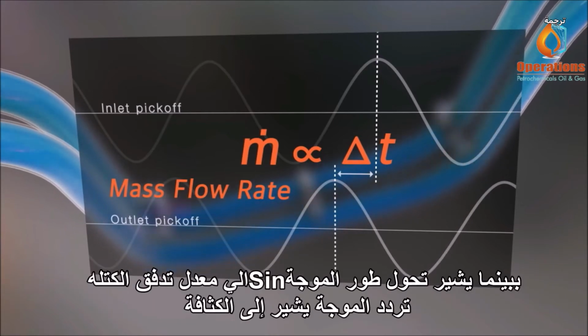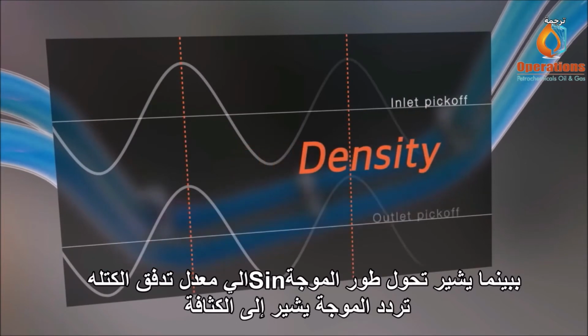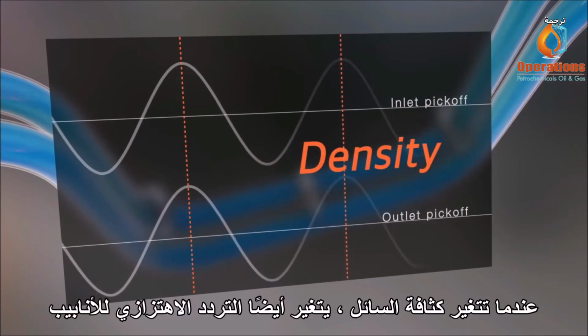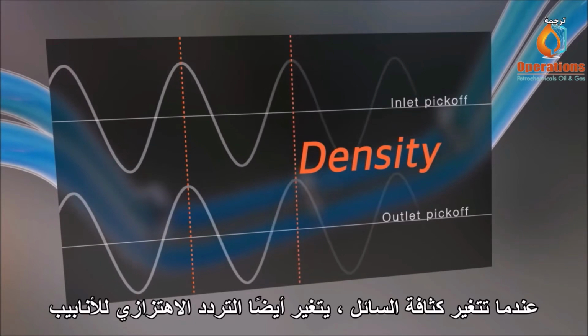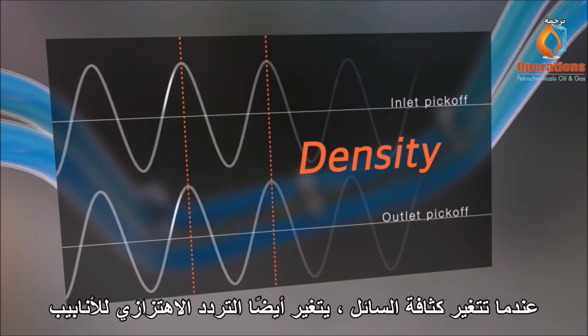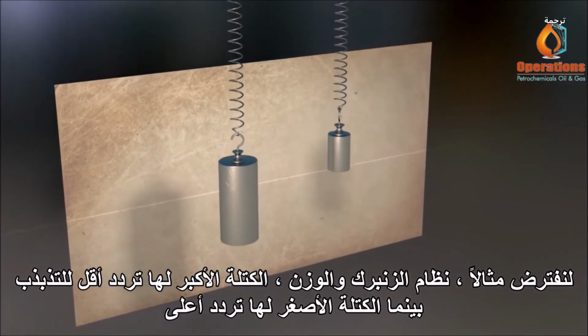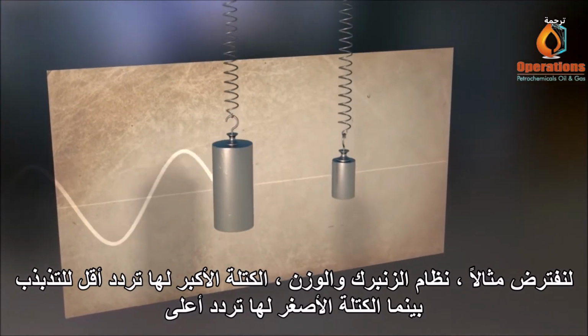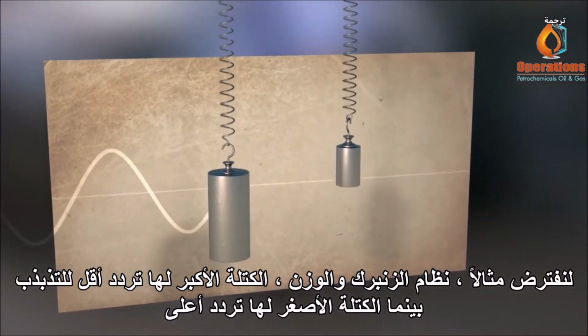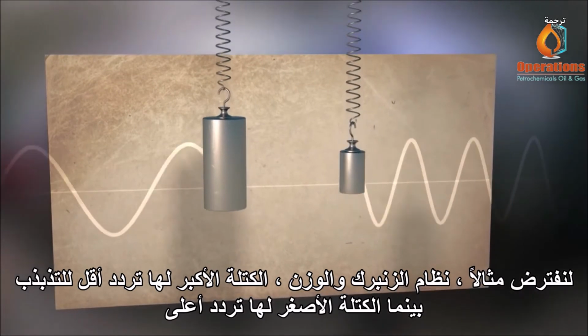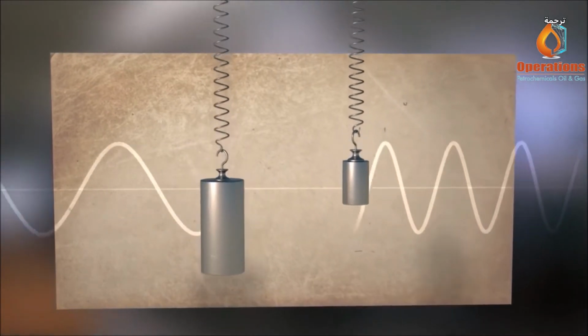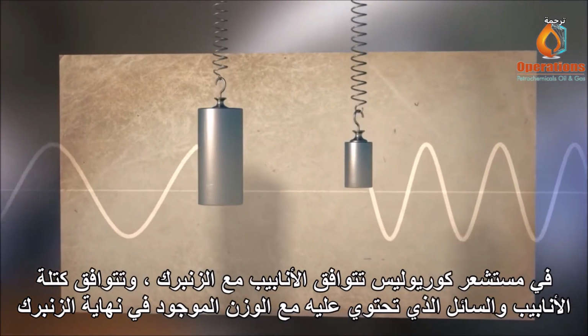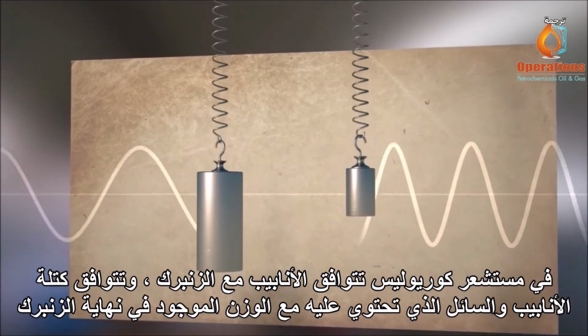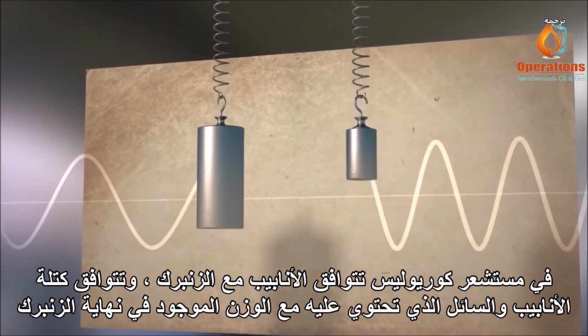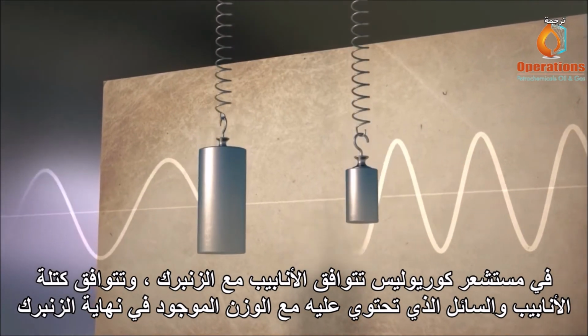While the sine wave phase shift indicates mass flow, the wave frequency indicates density. When the liquid density changes, the vibrating frequency of the tubes also changes. Consider an example of a spring and weight system. A larger mass has a lower frequency of oscillation, while a smaller mass has a higher frequency. In the Coriolis sensor, the tubes correspond to the spring. The mass of the tubes and the fluid they contain correspond to the weight at the end of the spring.